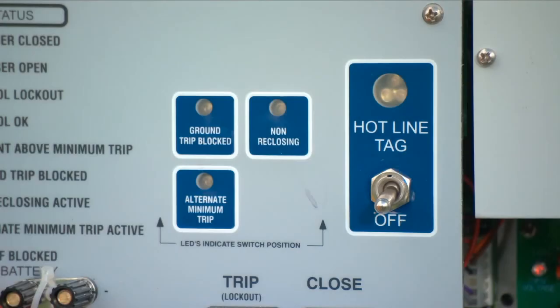Hotline Tag. Hotline Tag prevents all closing operations by opening control contacts in series with the recloser low-voltage closing circuit coil. If the feature is activated while the recloser is closed and the control is in the reset or home position, a fault will cause one trip operation to lock out.